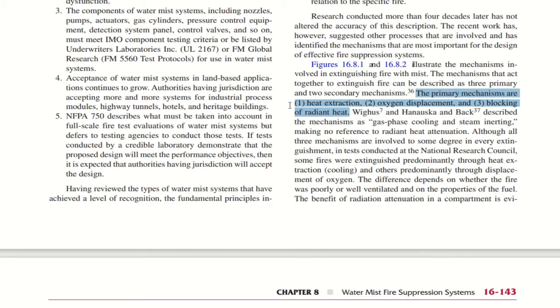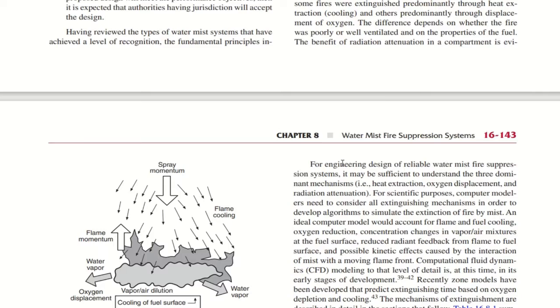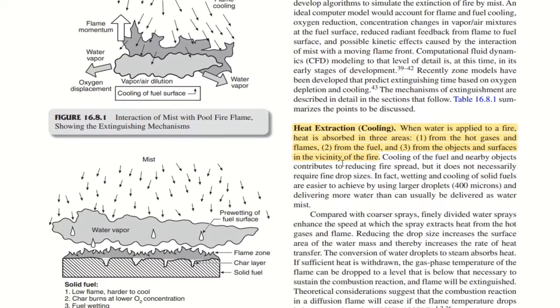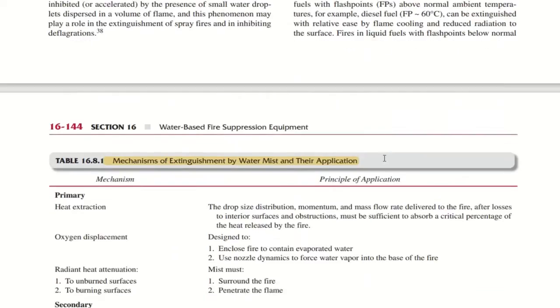The primary mechanisms are heat extraction, oxygen displacement and the blocking of radiant heat. This is an important point to be checked. And apart from that, I think there is one more point here regarding the secondary mechanism. You just go through it. Heat extraction: when water is applied to a fire, heat is absorbed in three areas: from the hot gases and flames, from the fuel, and from the objects and surfaces in the vicinity of the fire. So all these are available here.